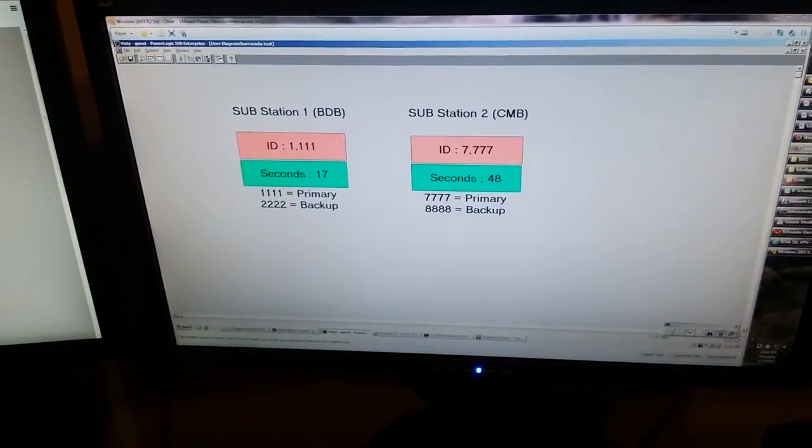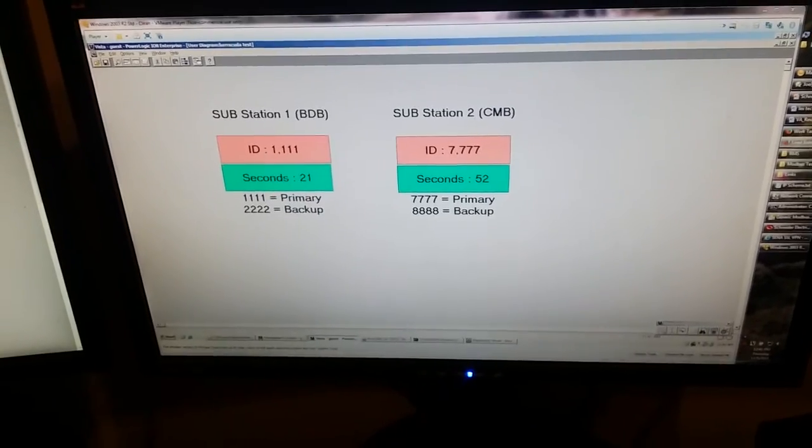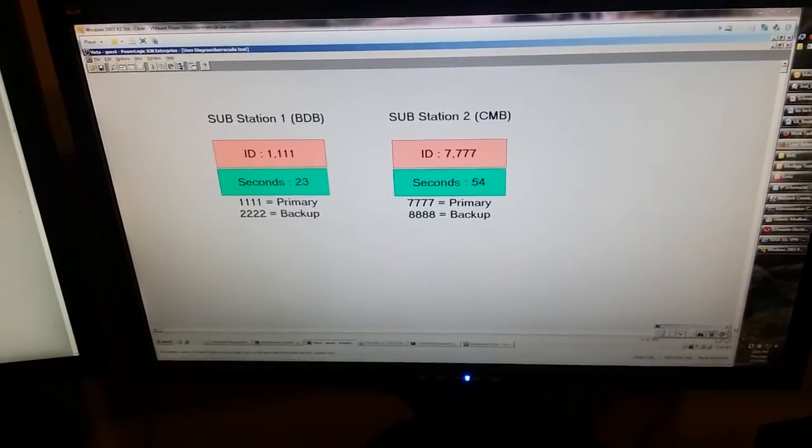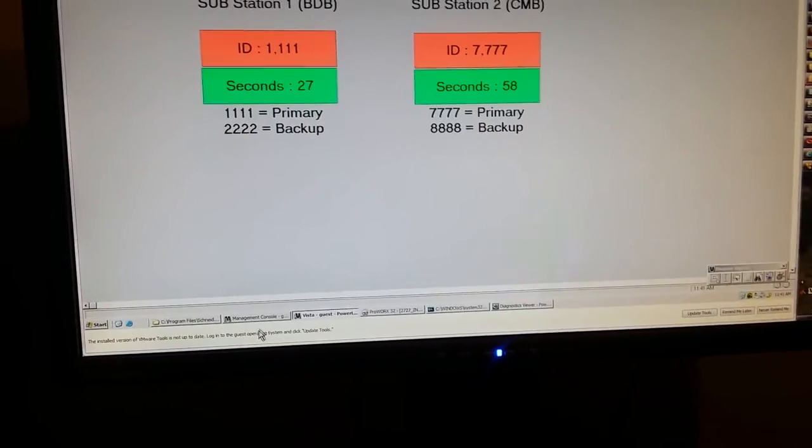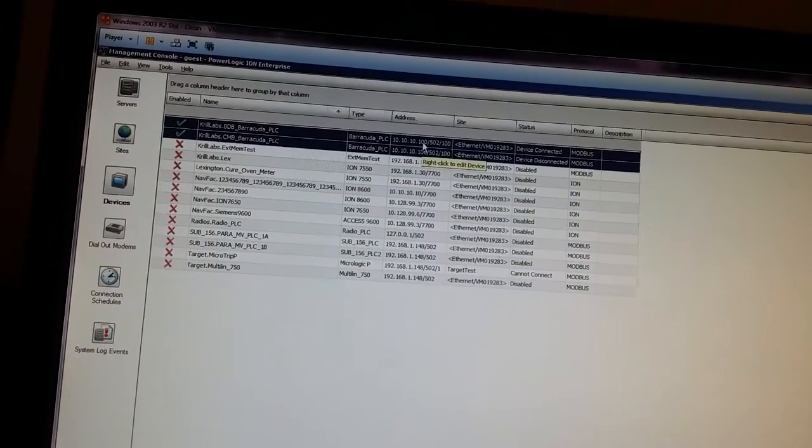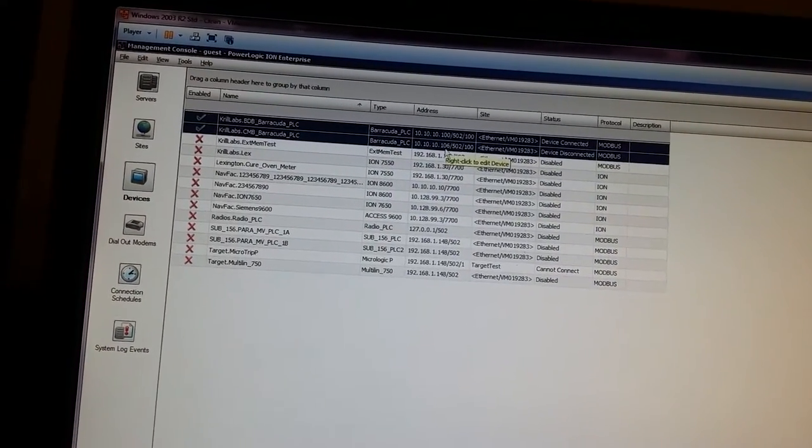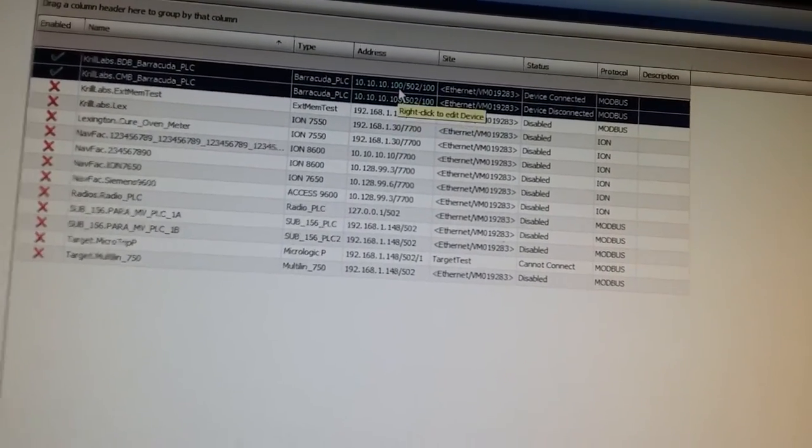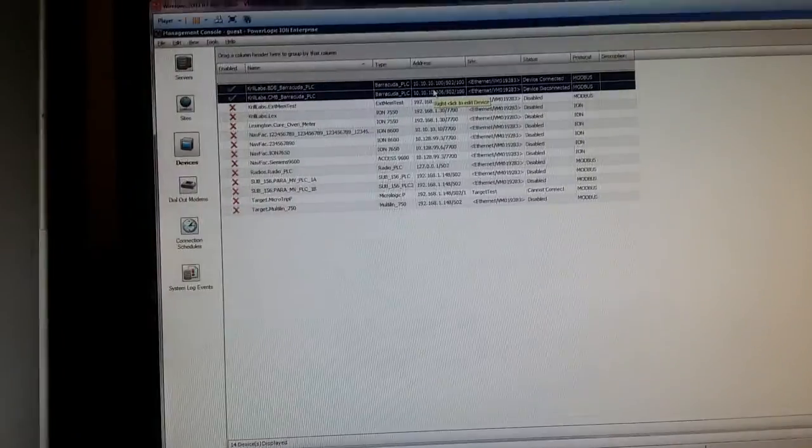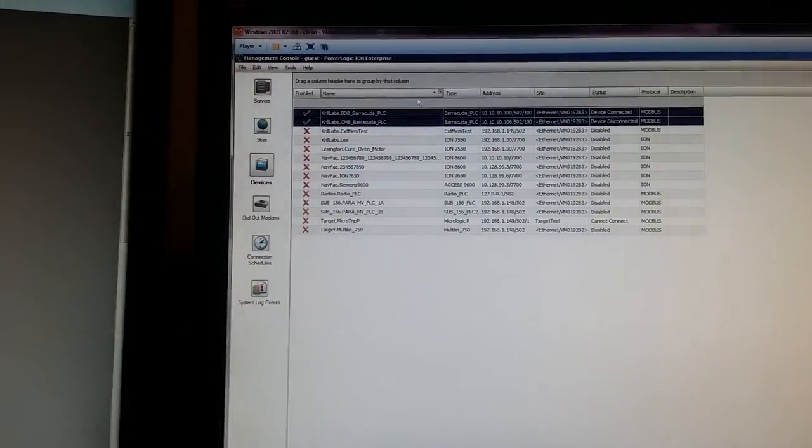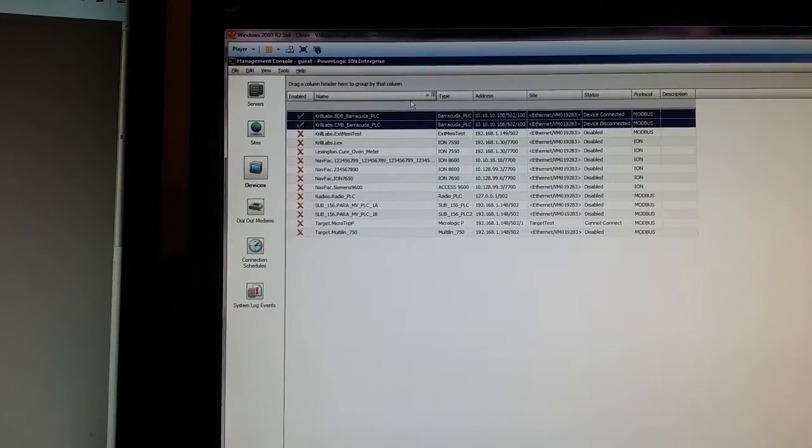This client was programmed to read some registers from each substation. Now it can only point to one IP for each sub, so we point it to the virtual IP. Here you can see the dot 100 for substation 1 and the 106 for substation 2. These are the virtual IP addresses. The load balancer will redirect us transparently to the active PLC. So let's see that happen.